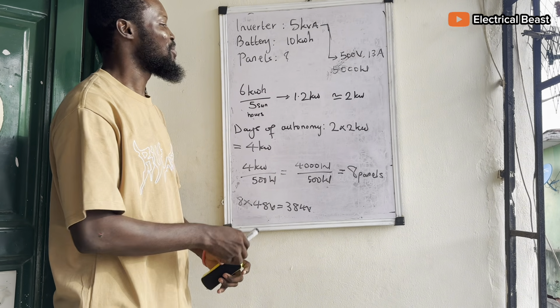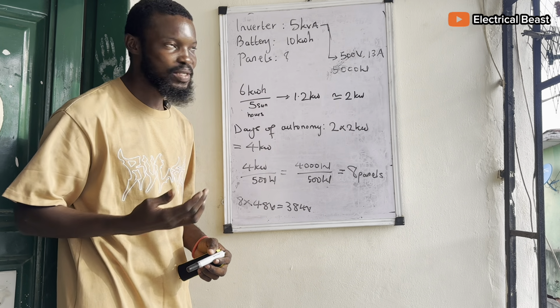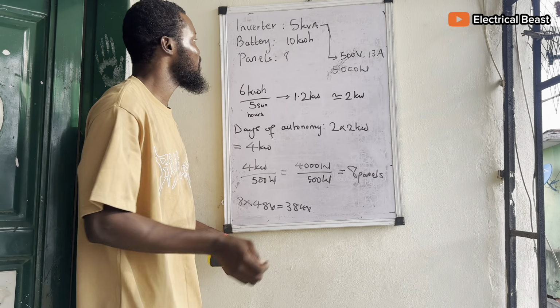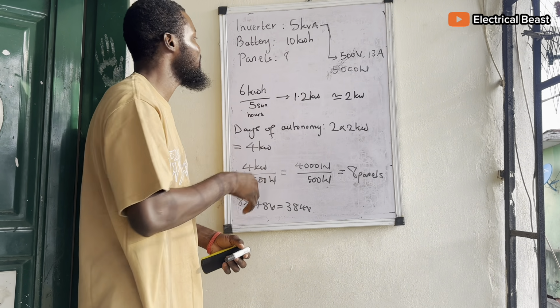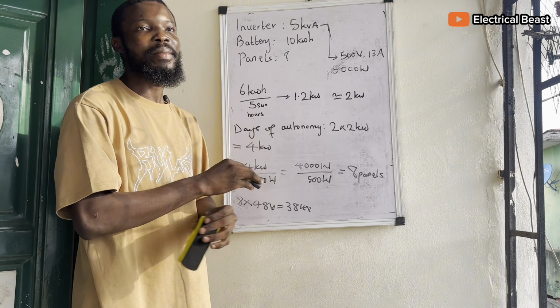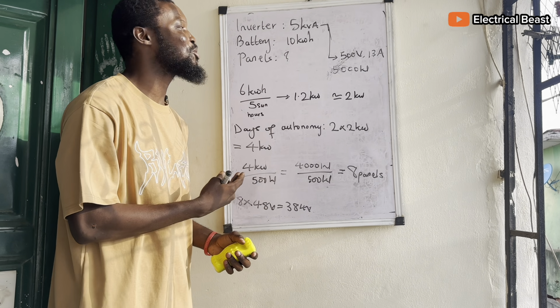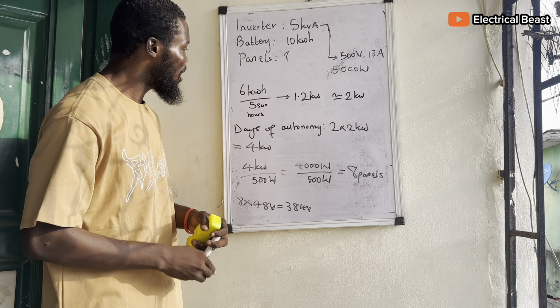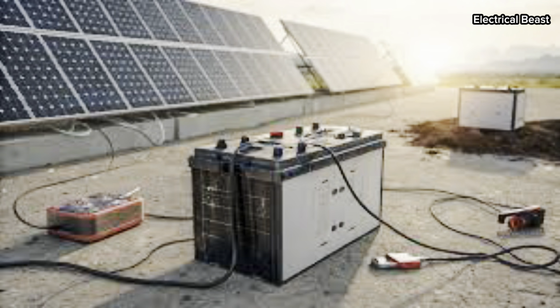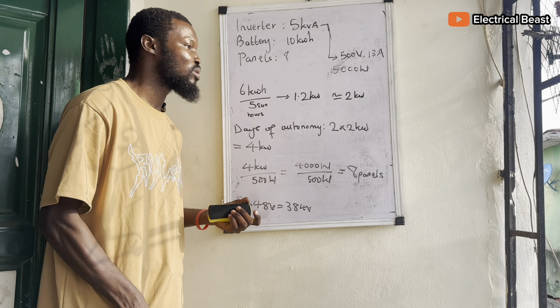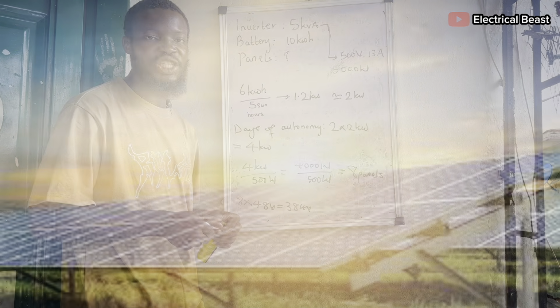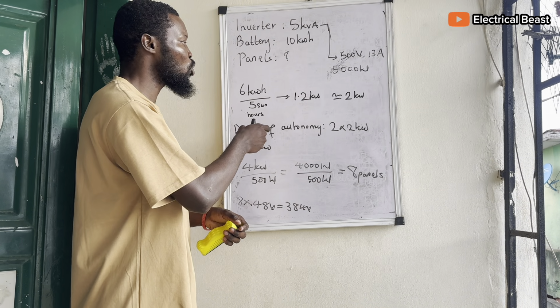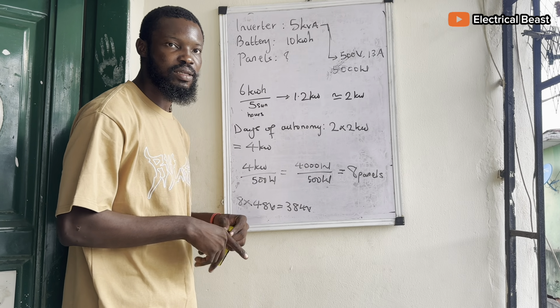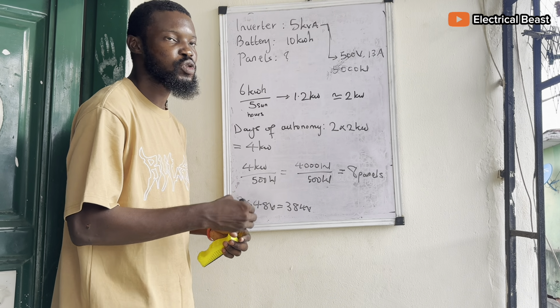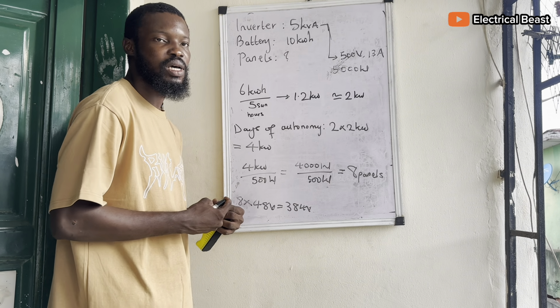All right, now we know to determine the inverter size, which is 5 kVA, and also the battery size, which is 10 kilowatt hour. Then we have the panels left. We don't need to bother about the charge controller because it's a hybrid system. The charge controller is inside the inverter. Now, how do you get the number of panels that is required to charge that battery? Okay, now the rule of thumb for the number of panels is that your panel should be able to generate at least the total amount of energy usage for that day within the required amount of sun time or sun hours.